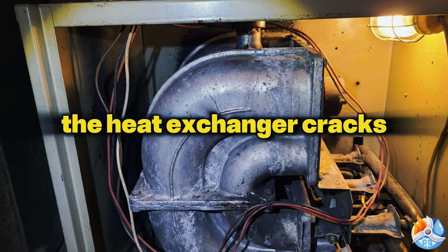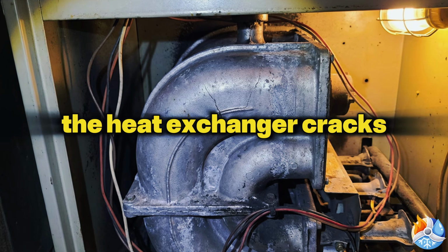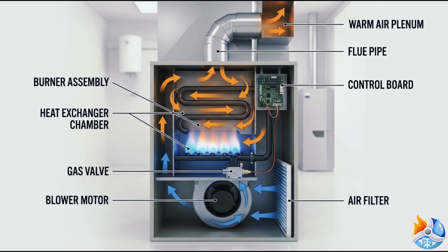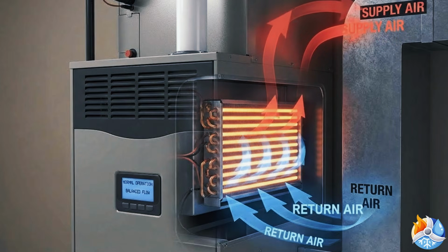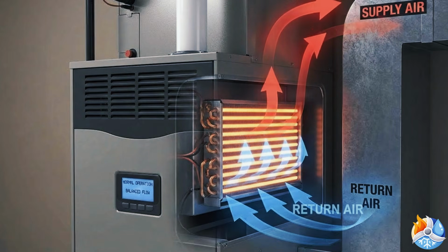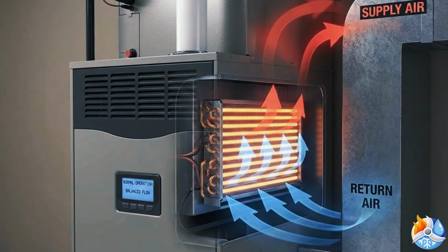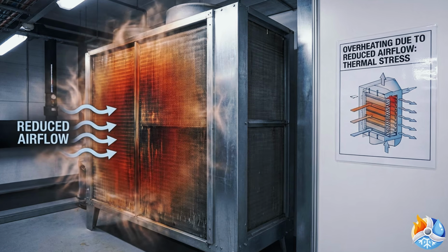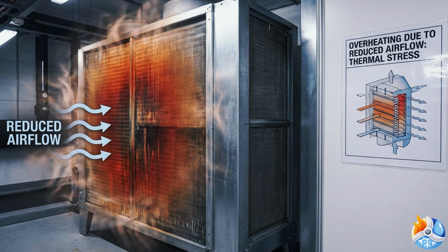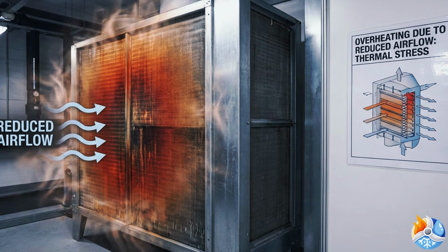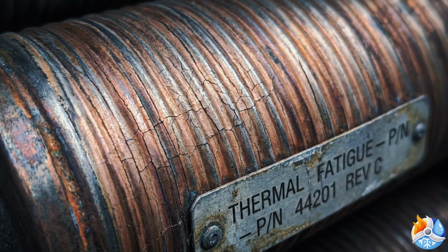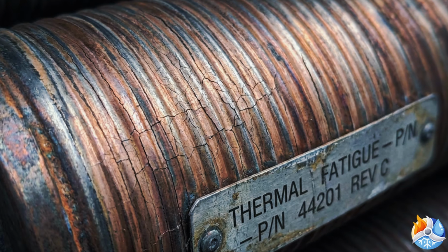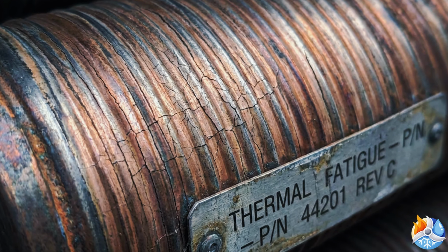Third, in gas furnaces, the heat exchanger cracks. This one matters beyond money. The heat exchanger is the metal chamber where combustion happens inside your gas furnace. It is designed to operate at a specific temperature, which depends on a specific amount of airflow running across it. Restrict that airflow, and the exchanger overheats on every single heating cycle. Metal expands and contracts over and over hundreds of times. Eventually it develops a crack.